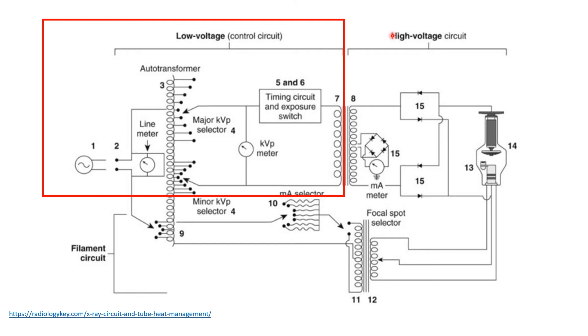AC power supply, the number one here, is provided by the electric power company. Next, is a main switch that controls the power to the control console. A line voltage compensator is present here, making sure that we have a precise voltage, usually 220 volts.